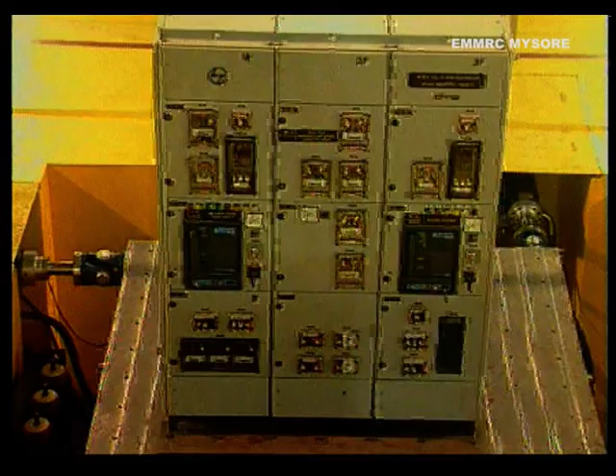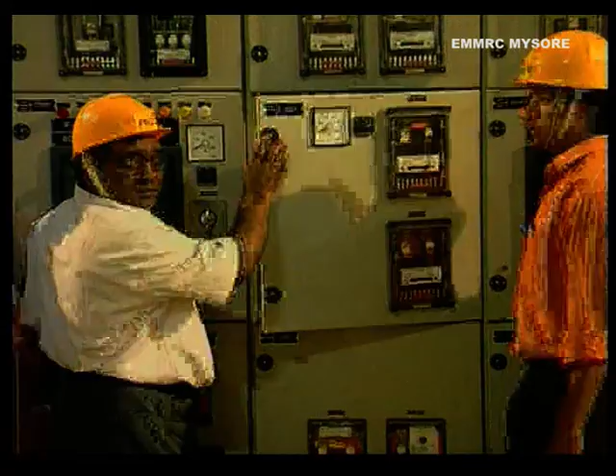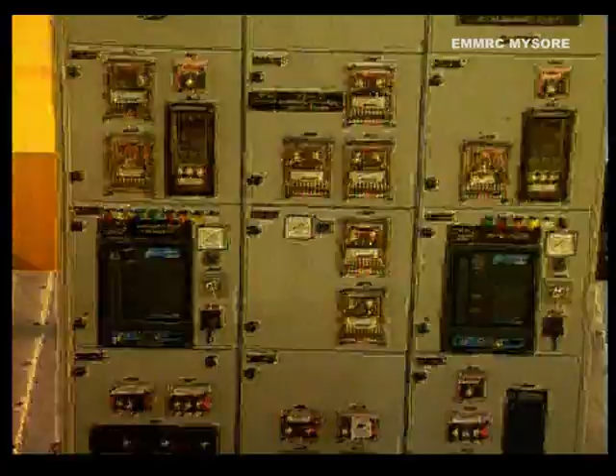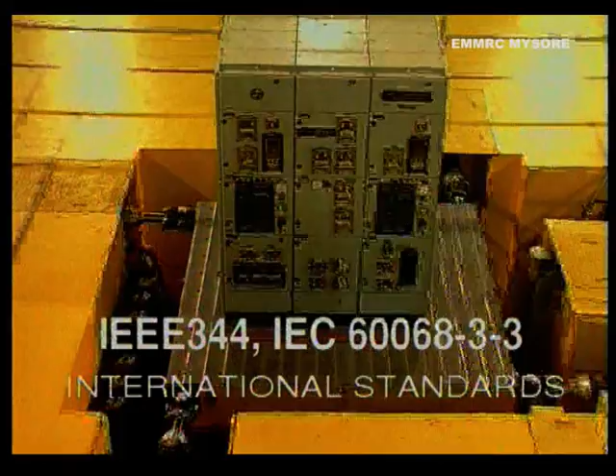Later, the same model is tested under working conditions for 30 seconds. The duration of the shake during an earthquake would normally be between 5 to 6 seconds. But here, the sample has to undergo a rigorous test for 30 seconds. After the test is over, the damage is inspected, analyzed, and a report in the form of a qualification certificate is given. The testing Triaxial Shaker System facility conforms to the IEEE 344, IEC 60068-3-3 and other international standards.